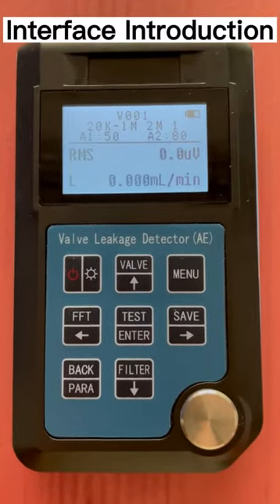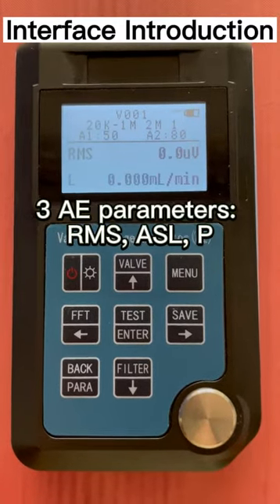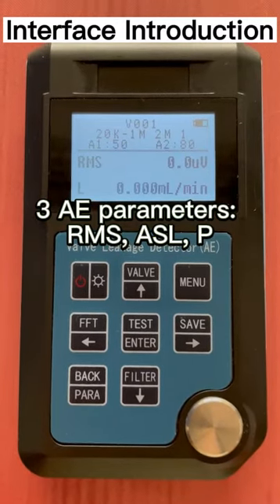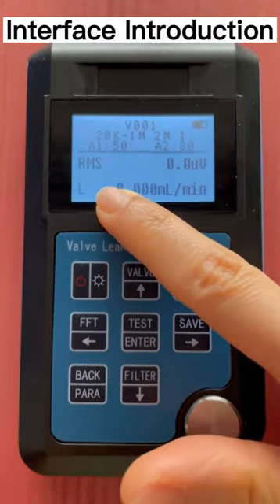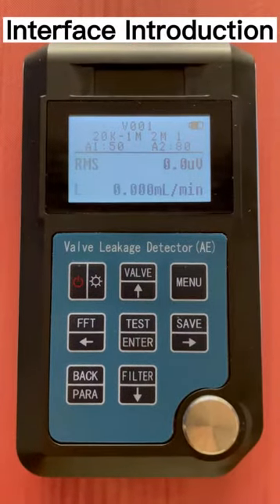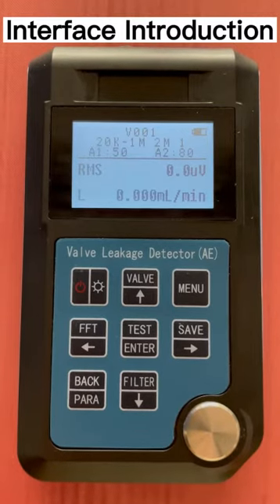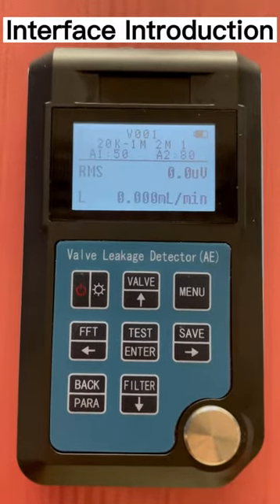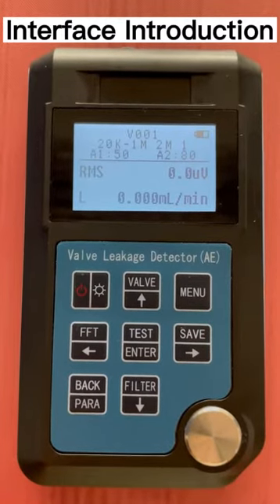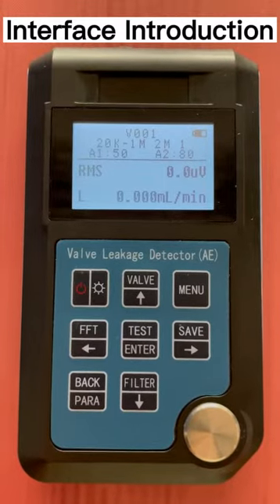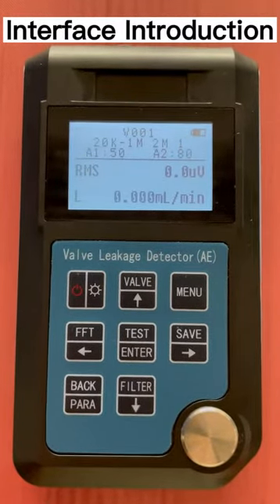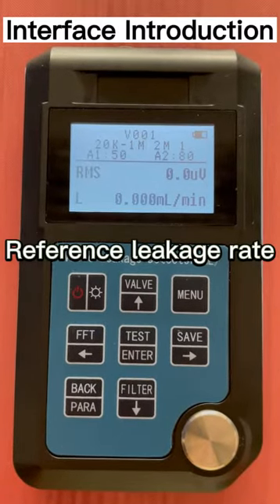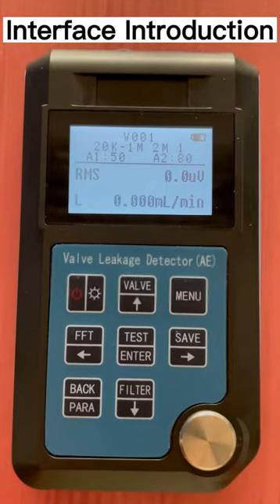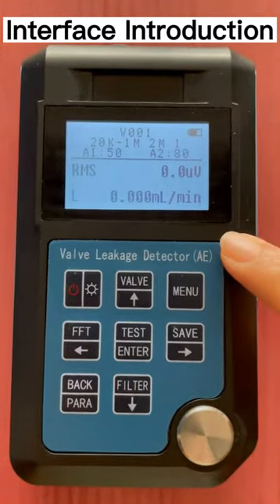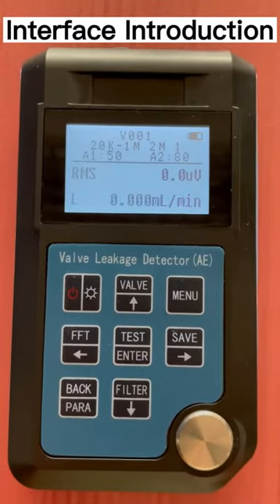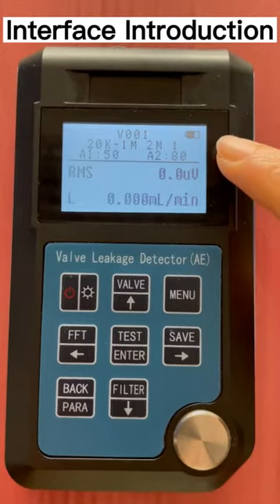The first row below the horizontal line is the measurement parameter, which can be RMS, ASL, or power. The value name is on the left, and the measured value is on the right. RMS is the root mean square of the acoustic signals in units of microvolt. ASL means the average signal level of the signal amplitudes in units of decibel. P means power in units of picowatt. The last row, L, means the reference leakage rate based on the calibrated parameter values. The value on the right is the reference value in units of milliliter per minute. The upper right corner is the battery level.